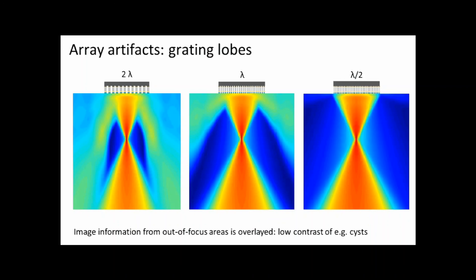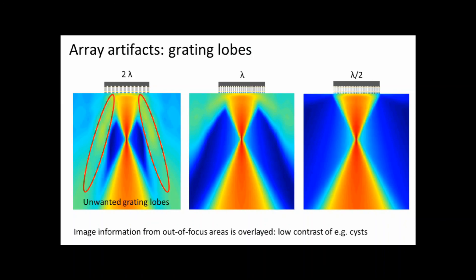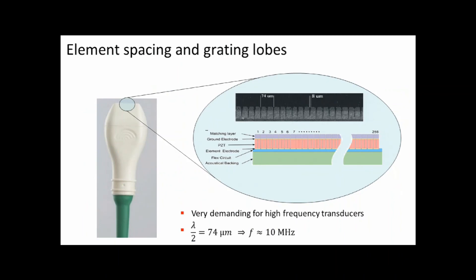Another artifact worth noting is grating lobes, relevant if you buy an ultrasound system and array. You can calculate the element spacing from the array width and number of channels. If the spacing is too large you get grating lobes, meaning when you intend to image one line you are simultaneously imaging lines at other angles. Ideally you want lambda-half spacing, but in small animal scanners this is very difficult to achieve — for example, you may need to cut 8-micron channels between elements with a laser. It is quite a challenge to produce small animal systems.